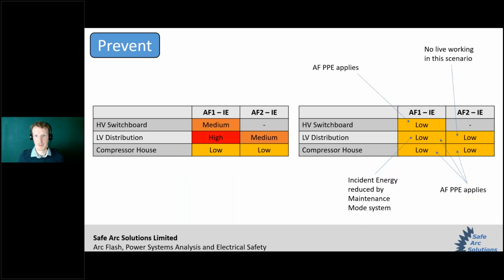So just to wrap up that prevent step, what you might do is go through a few iterations and come up with a few different strategies to bring down some of these highs and mediums to a more acceptable risk level. So say at the LV distribution, you identify that one of these maintenance mode systems would be the best way to deal with that high incident energy. That then allows you to make a sensible selection of PPE across the site, which brings down that residual risk.